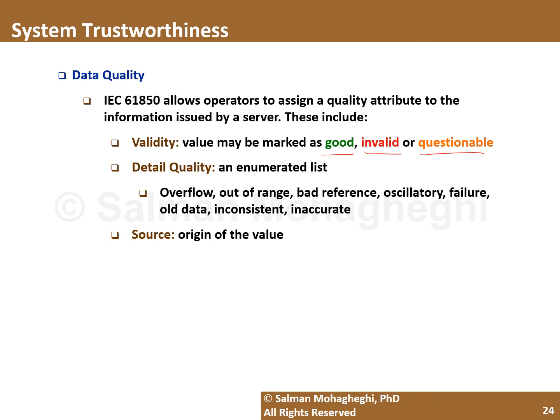For example, there is an overflow in the numerical value, the numerical value is out of range, or it's against a bad reference, or it has been oscillatory, going up and down, so I cannot trust that value. Or other things, for example, the data has been inconsistent or has not been updated for a long time. So that basically gives you additional information related to why that data provided by the device is questionable or invalid.